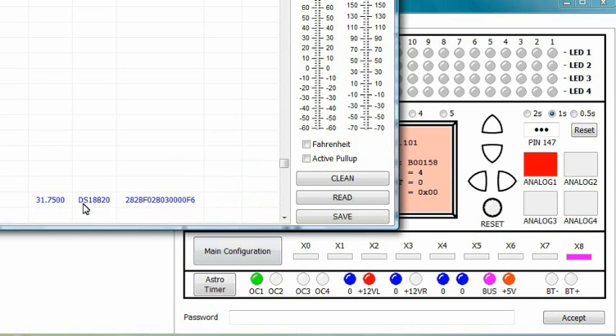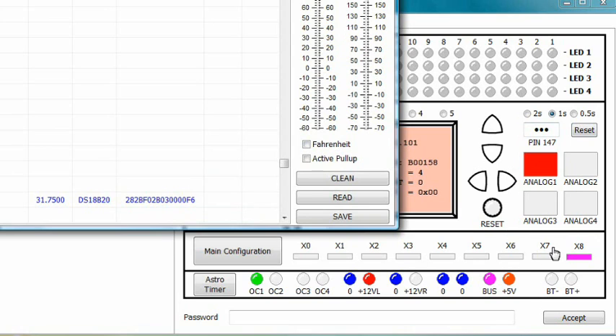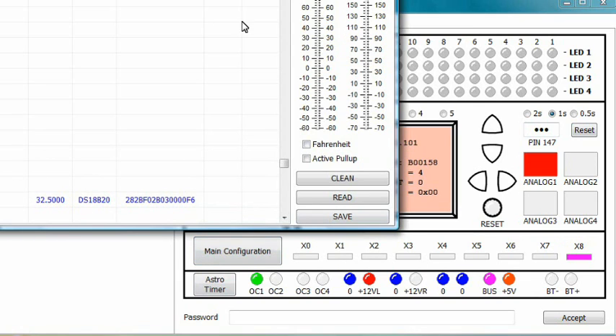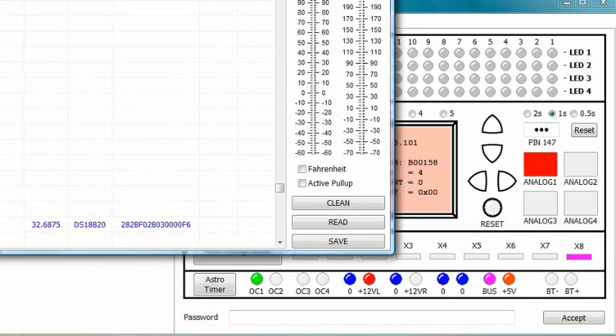As you saw, once the temperature fell below 32 degrees, it all started again. The analog zone was armed, the X8 variable was activated and the outputs were switched on, which again switched the heater and the temperature is now rising again. You can now exit this window.